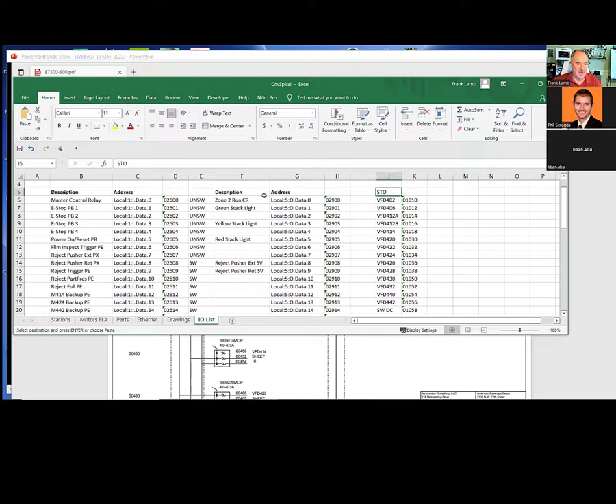Reject pusher, this is the thing that pushes the bottles off of the line if they fail the inspection. These are the outputs that tell the drives to run. These are the speed references. So these are 0 to 10 volt references. And then safe torque off. This list here is basically all safety wiring. And I did this for my own references as I was doing the drawings. So hopefully that answers your question, Abu Liban.